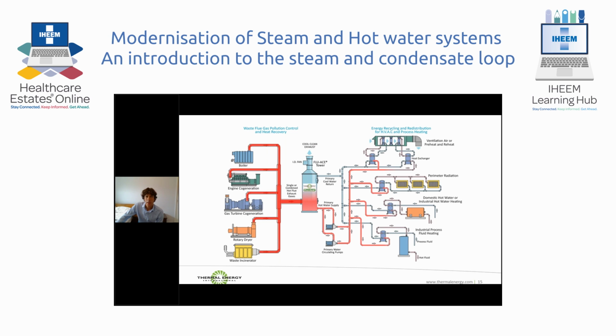The Fluways can be used to recover energy from a variety of sources: boilers, reciprocating engine CHP plants, gas turbine CHP plants, dryers and waste incinerators. Effectively, what you have with the Fluway system is a hot water heater, giving you hot water to use throughout the hospital, whether that be for HVAC systems for heating of the hospital, radiators in the heating circuits, or even better, domestic hot water and make-up water for the boiler. The colder the water we can bring into the Fluways tower, the more energy that we can recover. We can also use other heat sinks within the hospital, whether there's a swimming pool in the hydrotherapy unit, or catering requirements, laundry requirements, where they're on site in the hospital.